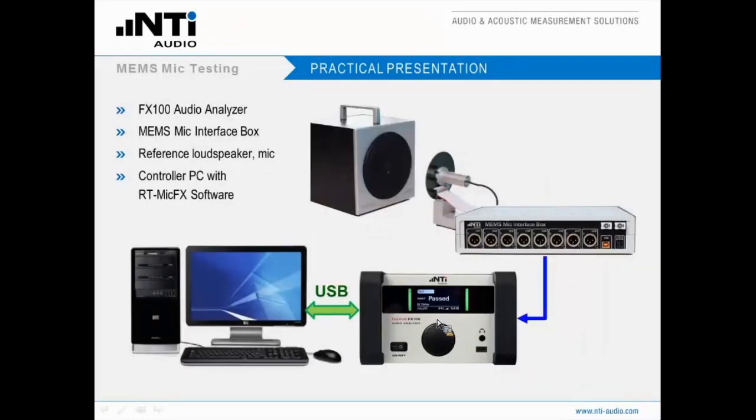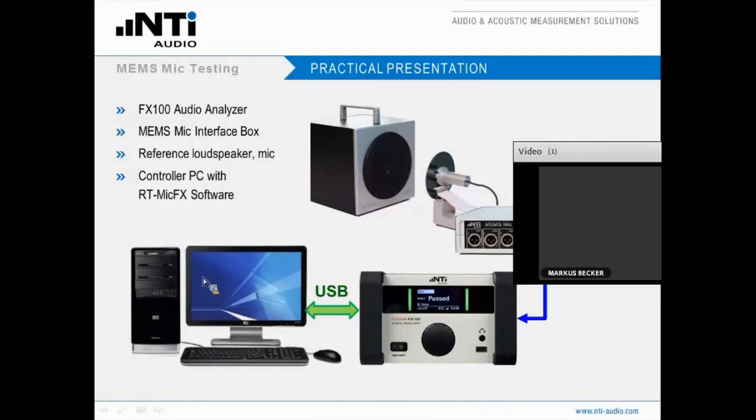So this brings us to our practical presentation. I have here on my desk an FX100 audio analyzer, a MEMS Mic Interface Box, a reference loudspeaker with a MEMS microphone and reference microphone, and a controller PC with the RT-MicFX software. I'm going to switch over to that, but before I just want to add a video webcam so that you can also watch the setup here on my desk.